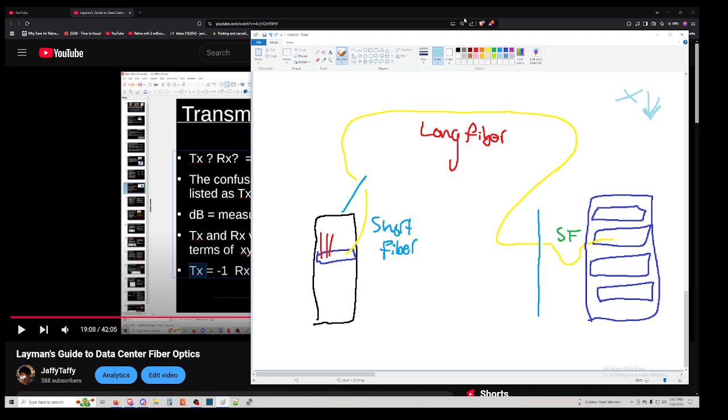And I've only seen on a handful of occasions, maybe less than 10 times, that it's ever been the long fiber. But you really don't want it to be the long fiber, because this rack could be on row A, and your brick could be in row G, and you're going to have to run all this fiber across a basket, make sure there are no kinks and no sharp bends and everything, and then reconnect it. And it was just so bad.